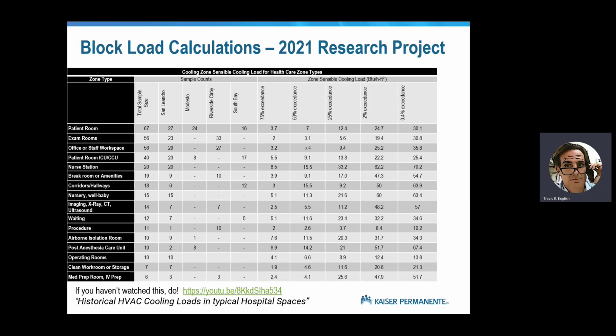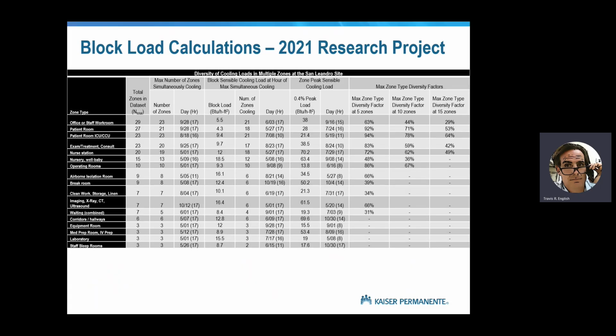To summarize this, on this slide, what you'll see is that we actually found the room peak loads in our ASHRAE style load calculations are pretty good. So in a patient room, the design engineer is going to calculate 30 BTU per square foot, and that's about what we found. At some point in the year, that room is going to peak out at 30 BTU per square foot. However, and you knew that I was going to say however, and this is the important part. When we do load calculations, we always assume that similar function rooms are going to peak at the same time. In reality, that is never true. So I had one of those dads that told me, don't say always or never. So I'm doing this very carefully.